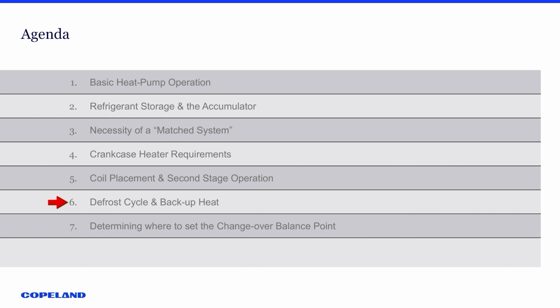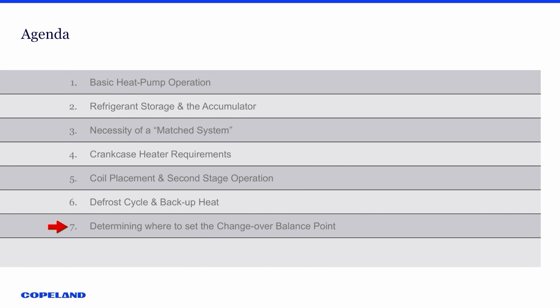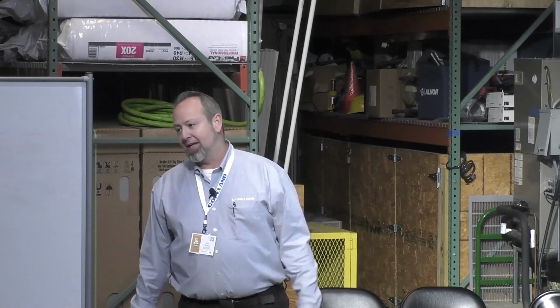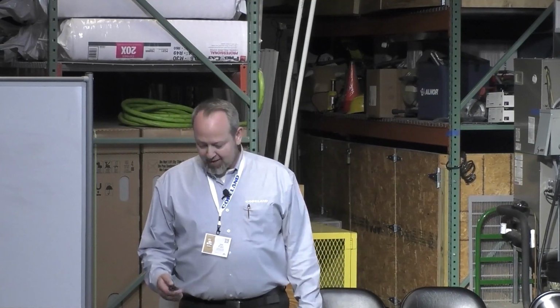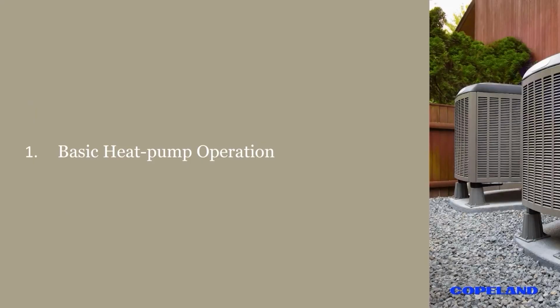Again, this is heat pump stuff. This is stuff you can take with what I call single fuel, electric heat pump and electric resistance heat. The dual of the fuel is just because you've got natural gas or propane or fuel oil or something like that, which back in the day we did a long time ago. And then determining where to set that balance point so that your homeowner doesn't get cold or the system just runs nonstop without keeping up. So those are our points that we want to hit today, and we'll have a cover slide for each one.